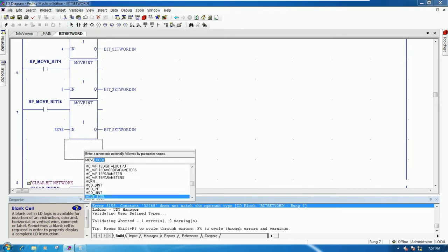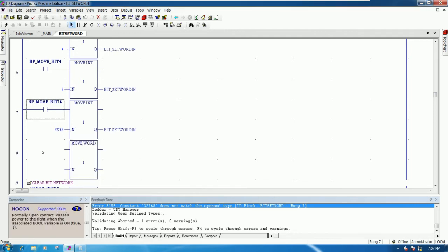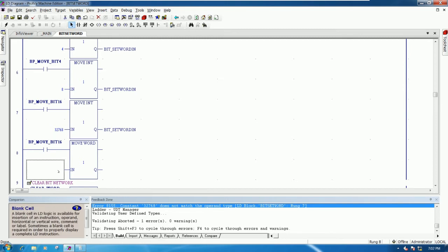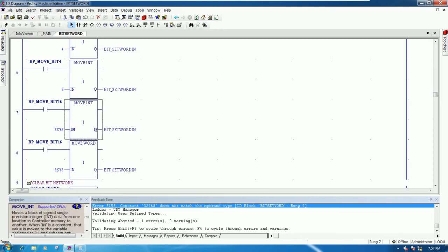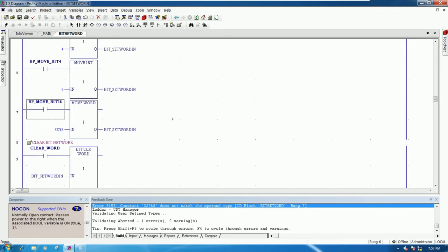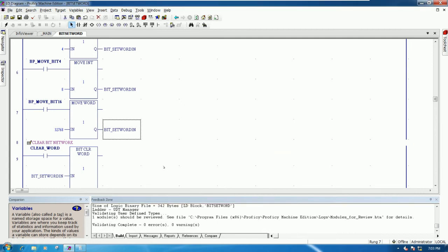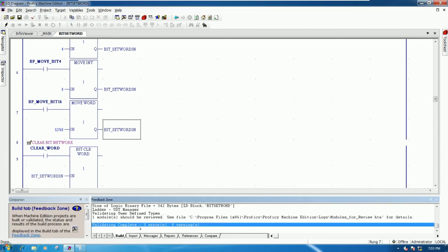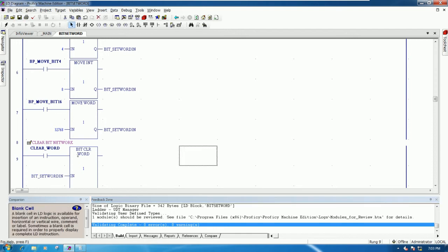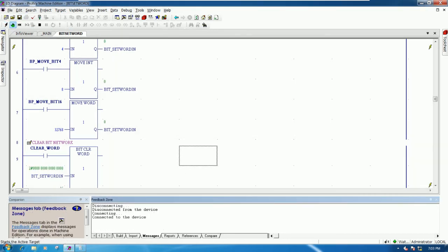To fix this, we should use Move Word instead of Move Integer, because when we convert decimal 32768 to binary it equals bit number 16. I will delete the Move Integer and use Move Word instead with the value 32768 to the word variable. Validate again - error zero. The error is gone.